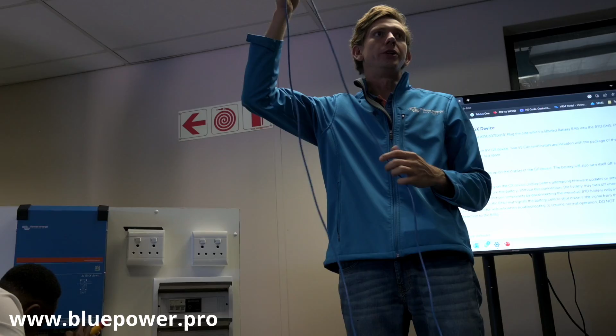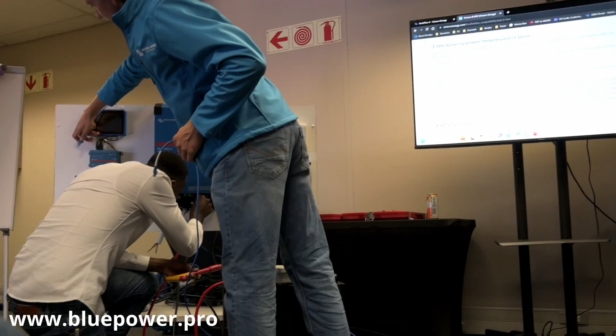So on the BMS CAN cable we've got 2 sides. One is marked Victron VE CAN, so that can go into your VE CAN if set up correctly, or into our BMS CAN because we've got a dedicated BMS CAN port. We'll put that one in on our BMS CAN, located furthest to the left on our Cerbo GX if mounted upright. And on the other side, the battery BMS CAN Type A will plug into our...